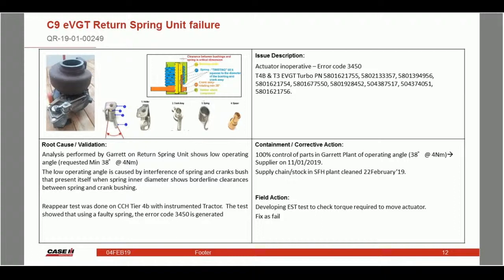We had to investigate all the parts coming back in. One step was to manually move the actuator separately, and we found a number becoming bound up. The spring sits on a shaft, and the spring itself was below tolerance. As the actuator opened, the spring's inner diameter reduced and it bound to the turning shaft. This increases torque, so occasionally the actuator cannot overcome it, or it becomes stuck in a certain position.